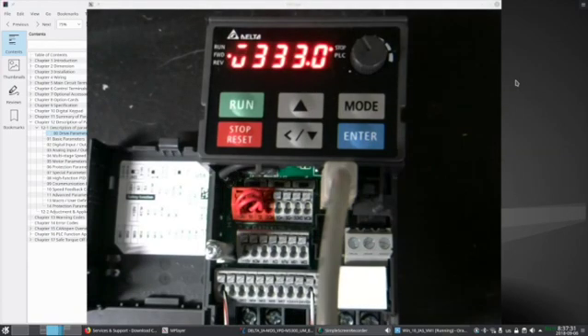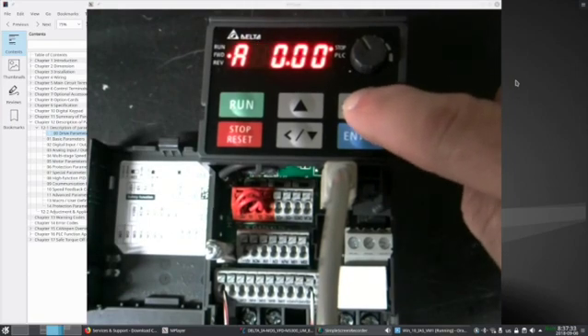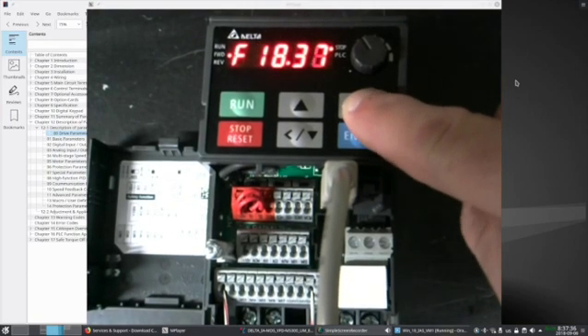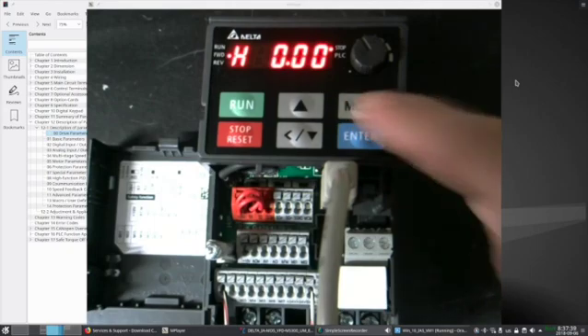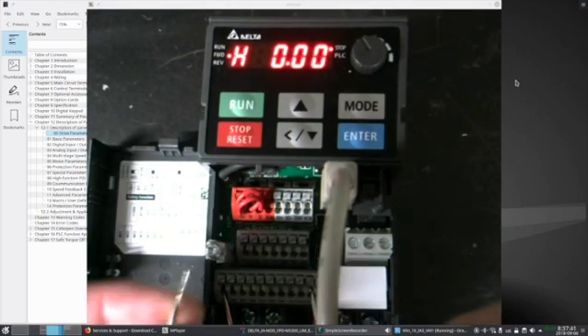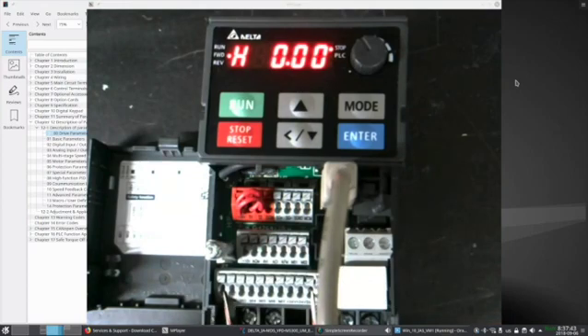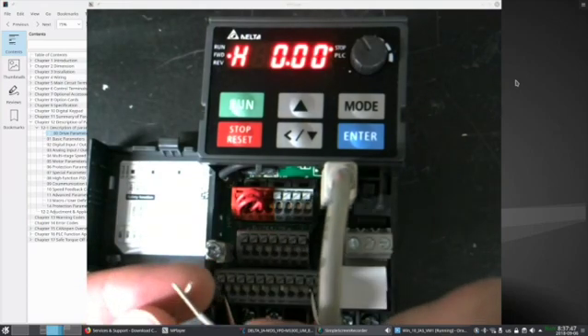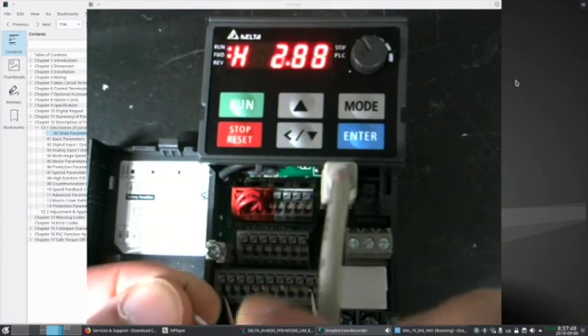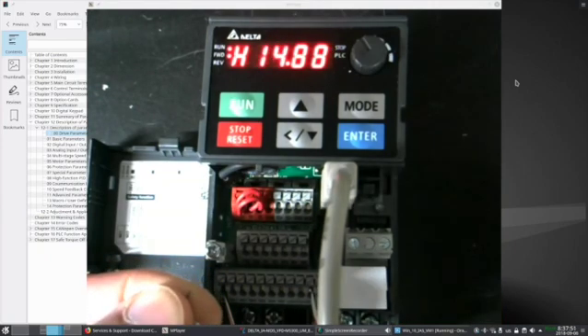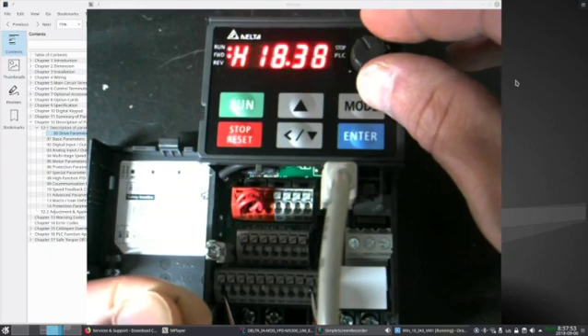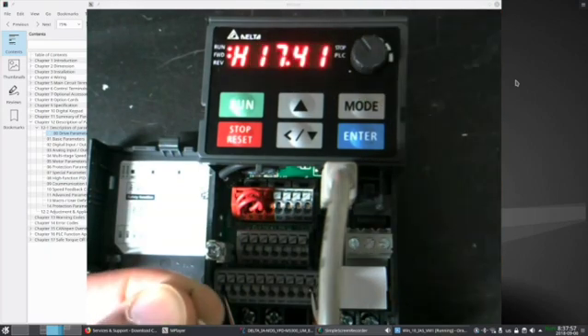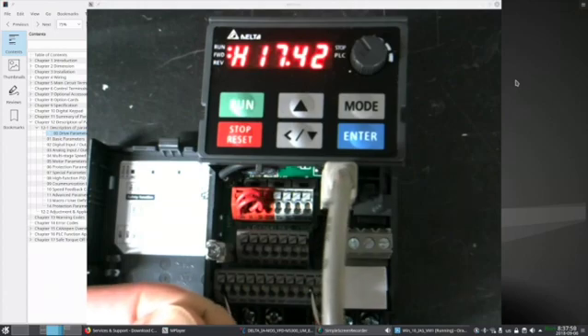Now for testing, the mode button will cycle me through monitoring different things on the drive. I'm going to look for the output frequency, H. Closing MI1 should give me a run forward command as indicated in the top left corner. I should have speed control with the knob on the parameter unit. And then disconnecting the wires should start my deceleration.